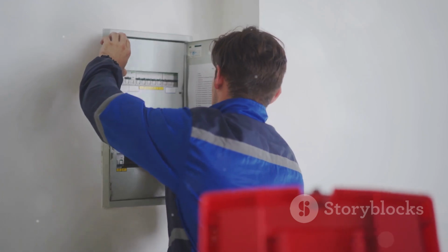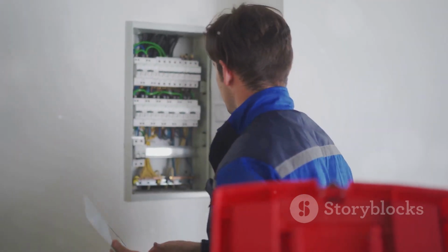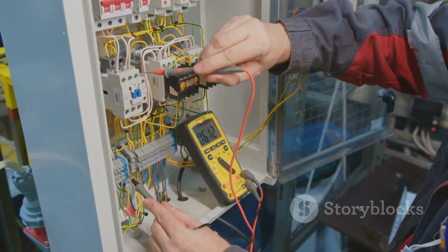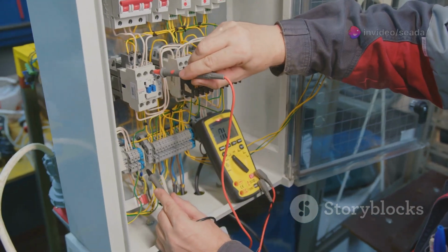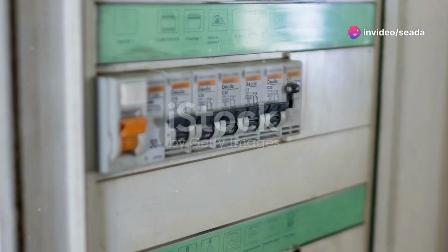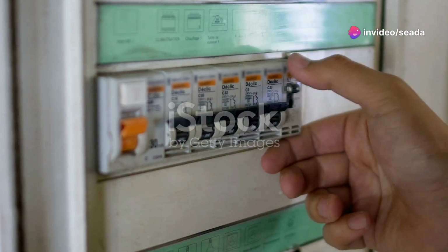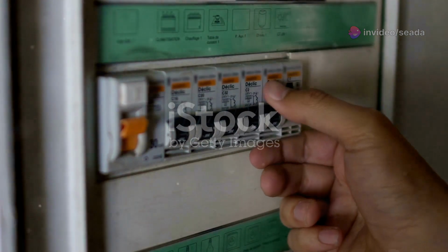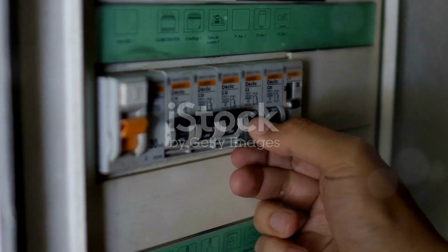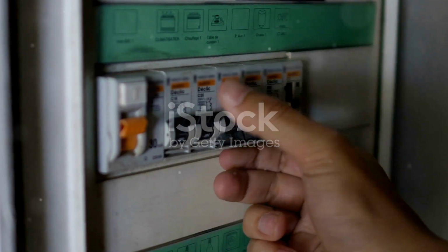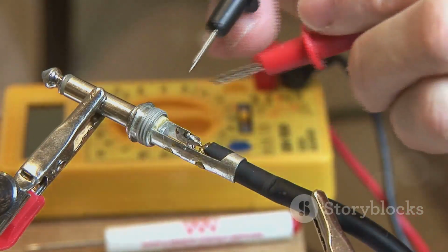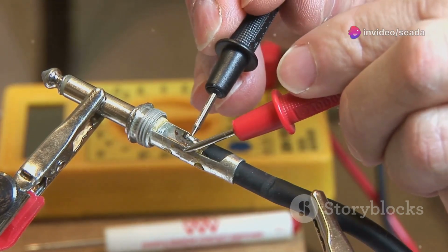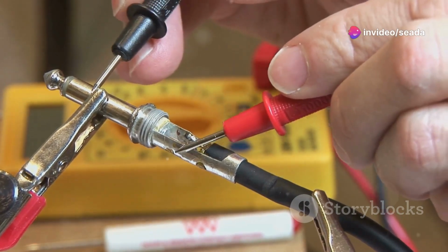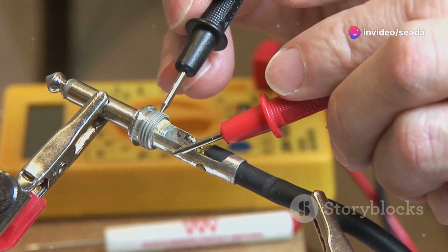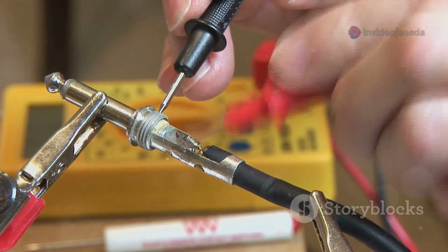Time to find the fault. When something goes wrong with your home's electrics, a multimeter is your best friend for tracking down the issue quickly and safely. You've isolated the problem circuit and switched off the MCB. This is a crucial first step to ensure your safety before you begin any testing. First, prove the circuit is dead. Use your non-contact tester on the MCB terminals.